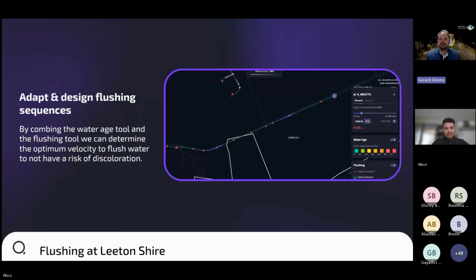A great example of this integrated approach is shown in this image: a 150 mil main on a 4 kilometre dead end. We have an automatic flushing station at the end of it, which reads from the chlorine readings. We use the hydraulic model to fine tune how the valve opens, balancing water turnover with the risk of stirring up biofilm and sediment.